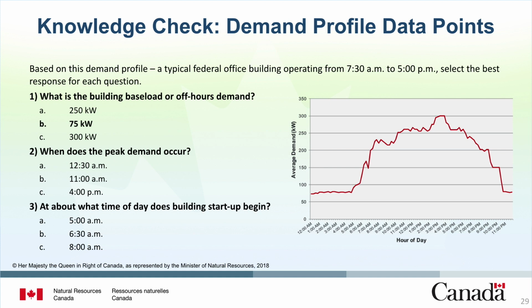The answer to question 2 is 4 p.m. The peak demand occurs at this late afternoon time and is likely a result of additional air conditioning load on a hot summer afternoon. The answer to question 3 is 5 a.m. Most buildings do start their systems before the scheduled occupancy to make sure the space is comfortable for occupant arrival. However, given that this building is not scheduled to be occupied until 7:30 a.m., the 5 a.m. startup may be an opportunity for efficiency.